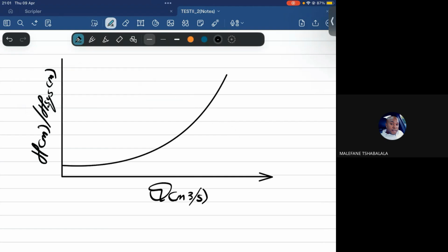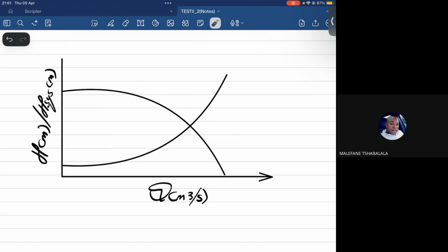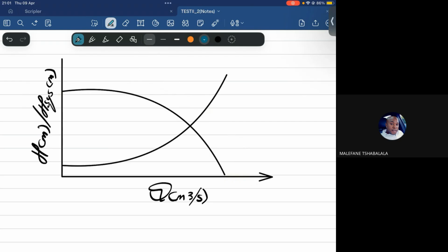It's fine. So I'll have the characteristic curve of the first pump, and then since now these pumps are connected in parallel, in order for us to get the second characteristic curve, we have to multiply the readings of the volumetric flow rate by 2, meaning that our graph of the two pumps that are connected in parallel will look like this.